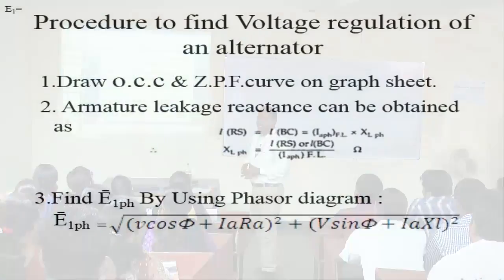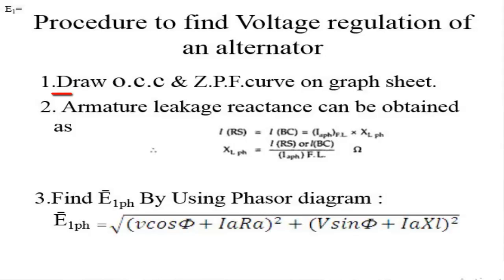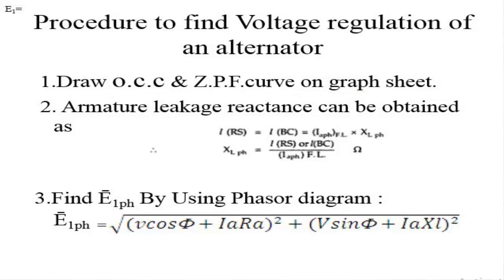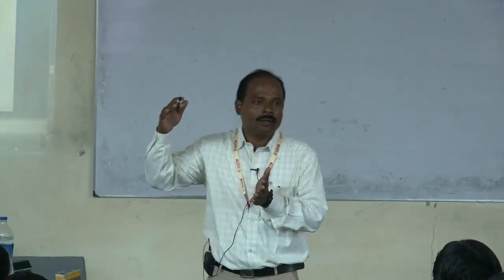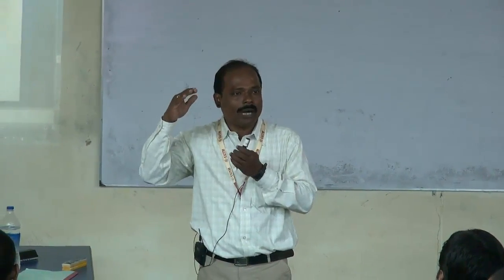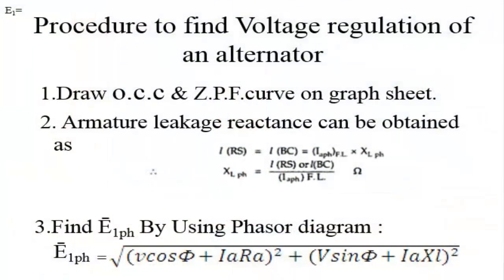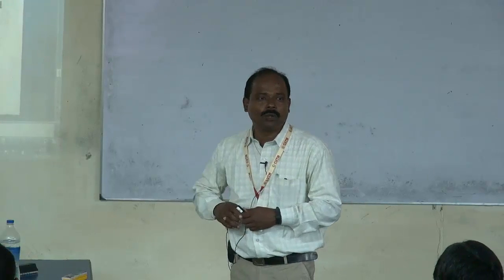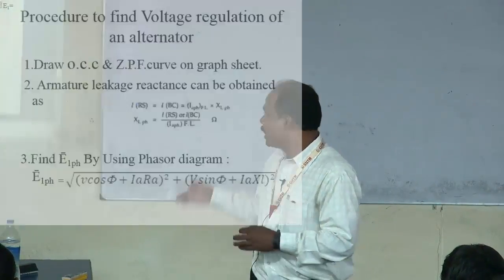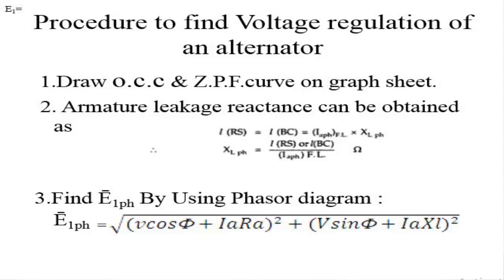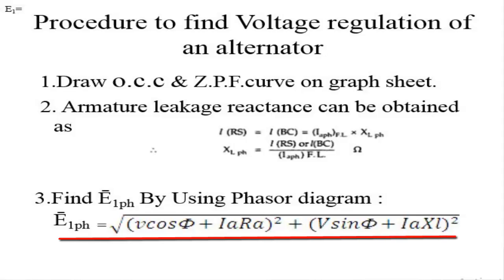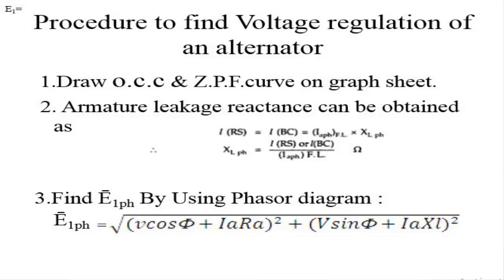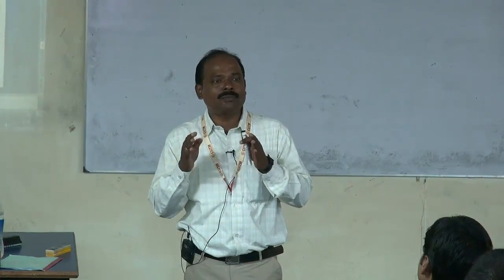The step-by-step procedure for voltage regulation by ZPF method is as follows. Step 1: Draw both the OCC and ZPF curves on the graph sheet. Step 2: Find the IA XL drop from the graph using the Potier triangle — XL equals length of RS divided by full armature current. Step 3: Using the formula E1(ph) = √[(V cos φ + IA Ra)² + (V sin φ + IA XL)²], calculate E1, the voltage induced allowing for armature reaction drop.